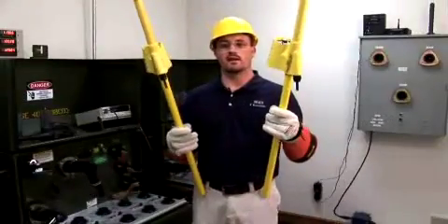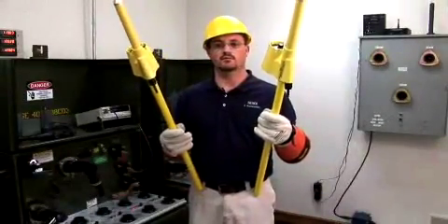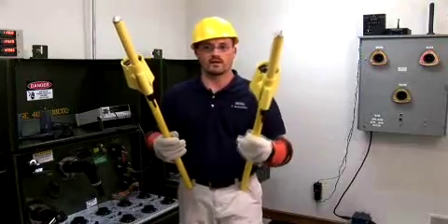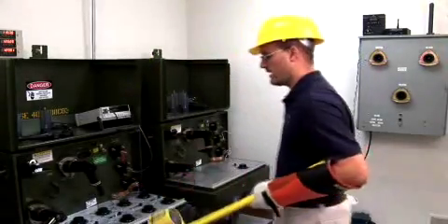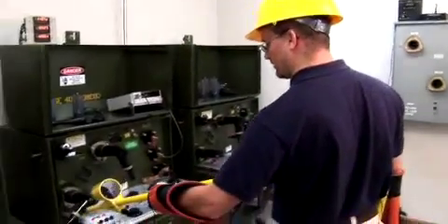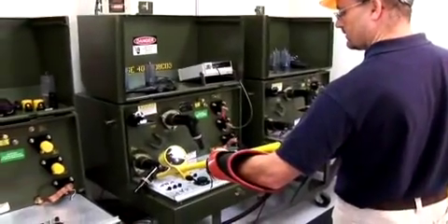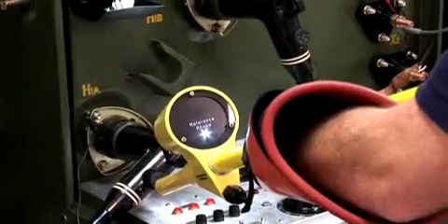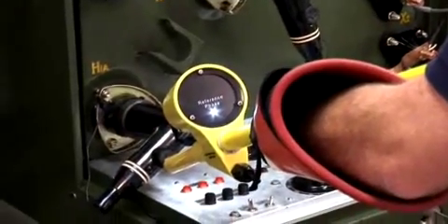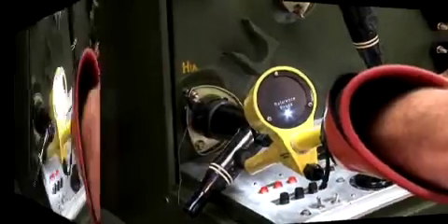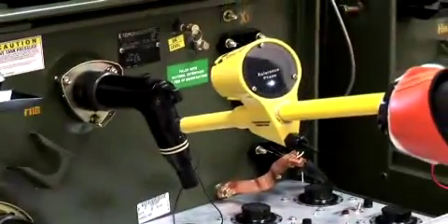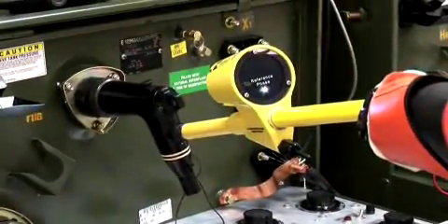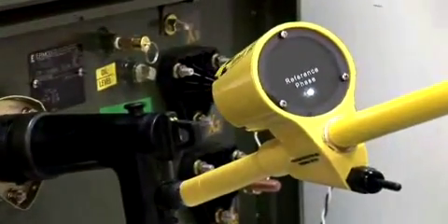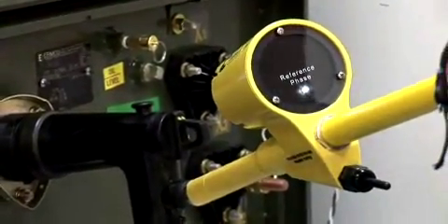Now we're going to use the PD800W to phase capacitive test points. Before we phase, you can use the reference probe as a single point voltage detector to determine if the test point's energized prior to phasing. So we get a white light indicating that this elbow is energized. Moving to the next elbow, same thing. We get a white light, we're energized. And the last, we get a white light, so we're energized on all three elbows.